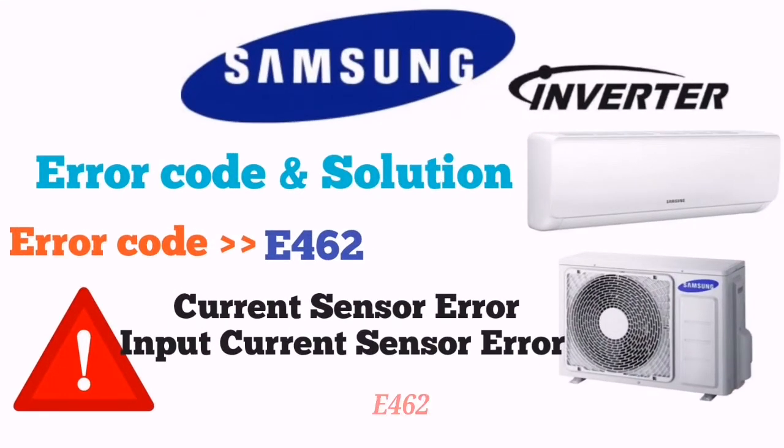When you see error E462, or your LED 1 and LED 2 are blinking and LED 3 is on, it means current sensor error or input current sensor error. At that time you have to check the PFC shunt and IPM shunt resistance value, whether it is correct or not. If it is not correct, then you have to change the outdoor PCB and your unit will be in working condition.